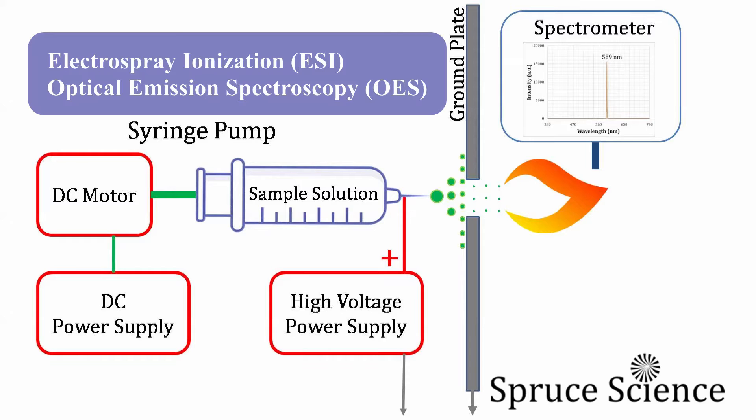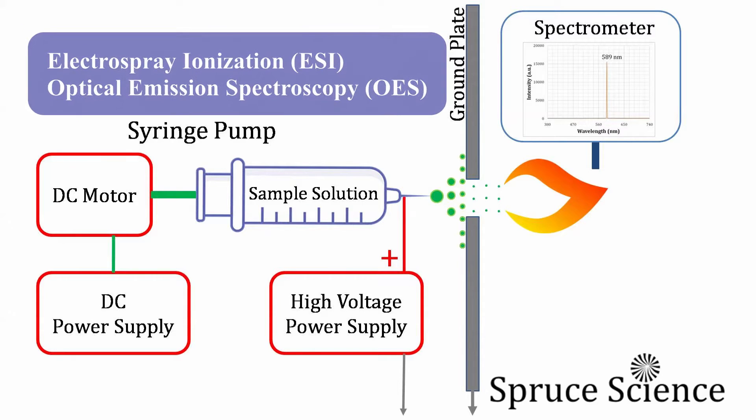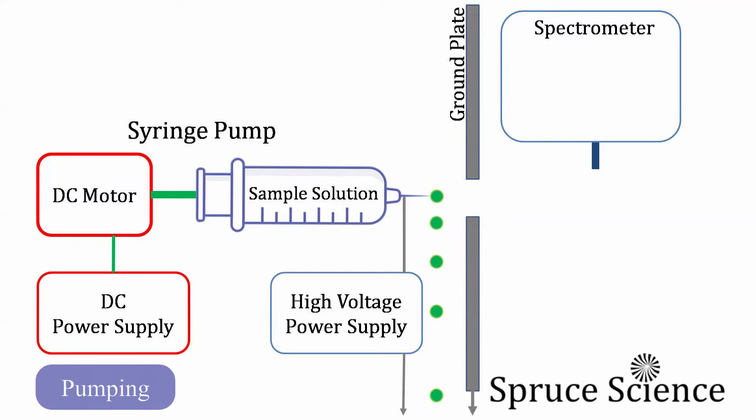Let me explain a little more about this two-step process using the schematic illustration you now see on the screen. The left side of the ground plate is where electrospray ionization takes place. The sample solution is loaded inside a syringe pump and a DC motor slowly pushes the liquid through the needle.